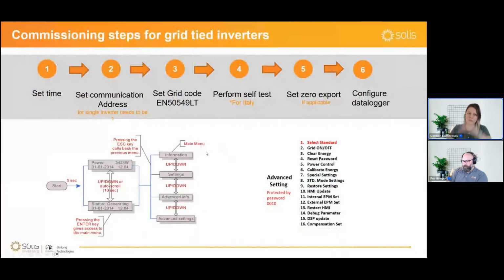In terms of commissioning, I'm going to go quickly through the steps. For the grid-tied inverters, I think everyone knows that it shouldn't be much of a job in terms of setting up an inverter. The only thing you might have to make sure of is the correct time and the correct communication address. This is important if you are connecting to a data logger. When you have a single inverter, you want the communication address set to 1. If you have multiple inverters, of course, each one needs a distinct communication address. Then set the grid code, but usually if we deliver inverters to a certain country, we send them with the grid code already preset.